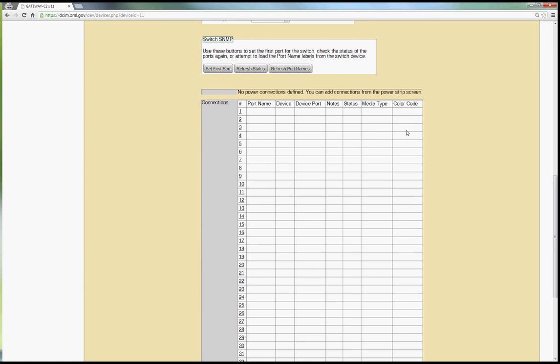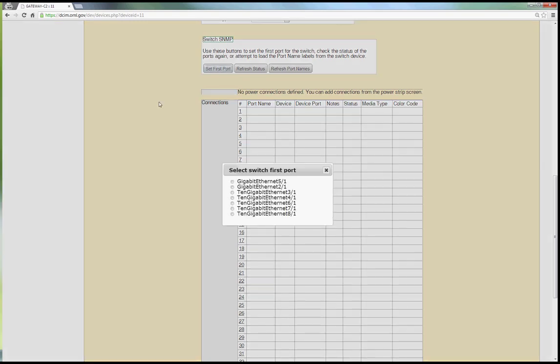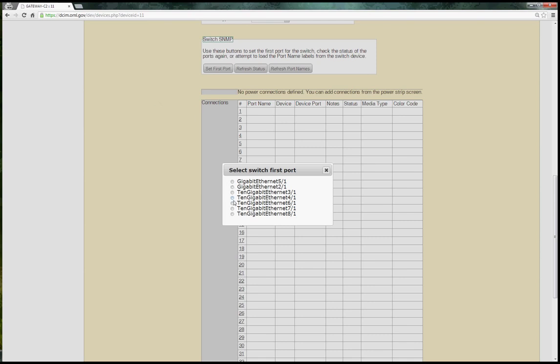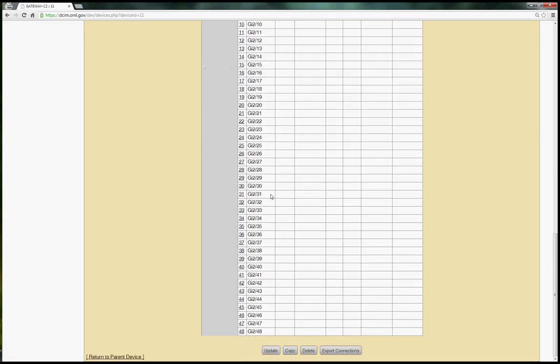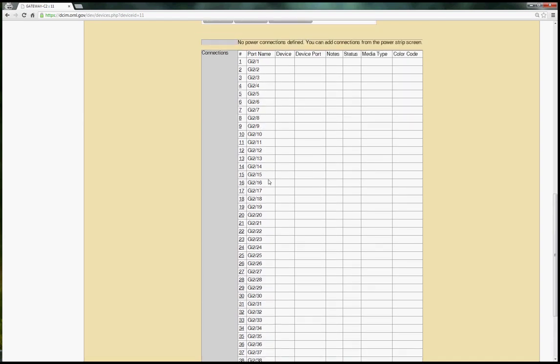So let's take a look at how we can talk to some of these devices and actually pull those names from the card itself. So in this particular chassis I've actually got 1, 2, 3, 4, 5, 6 cards. And when I click set first port open DCIM talks SNMP to the IP address which happens to be the management interface for this chassis and it's showing me all of the different cards that are in there. And we're not really sure which one there is or that you're referencing so we're having to get a little bit of human interaction but as soon as I click gigabit ethernet 2.1 it's going to pull it and it's going to get the port names for all of those ports. So this is the port name that your network engineer would be very familiar with and would be very happy to know that you are starting to reference.